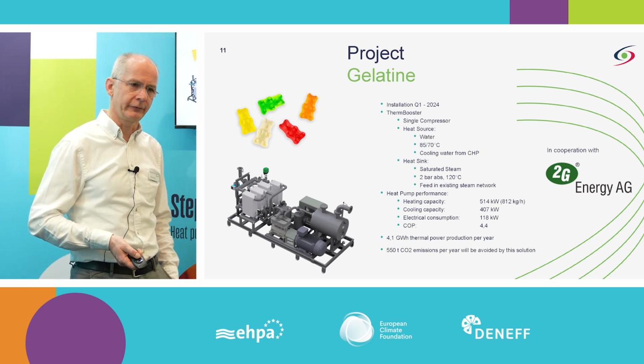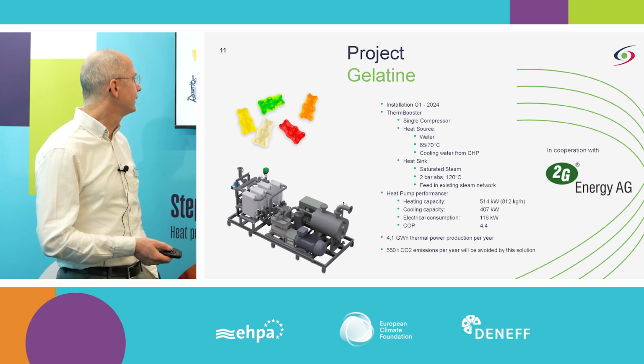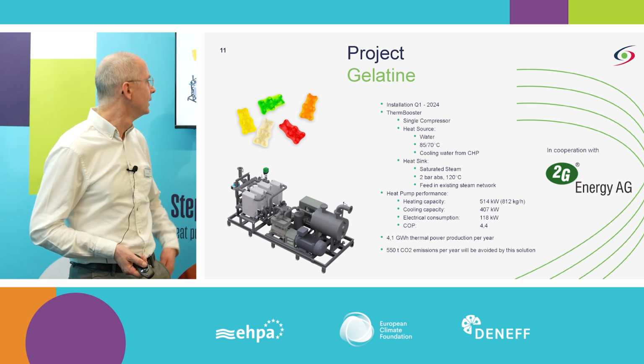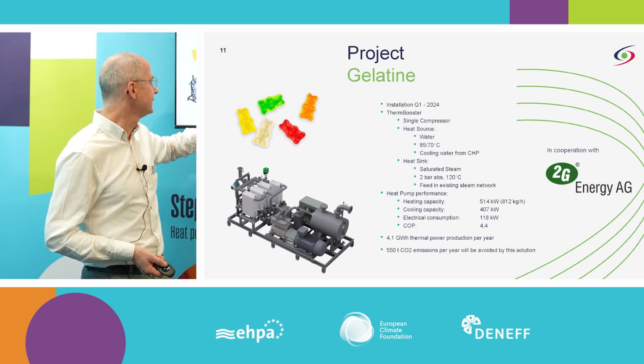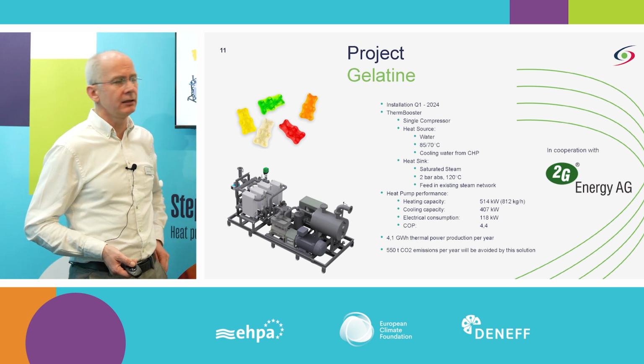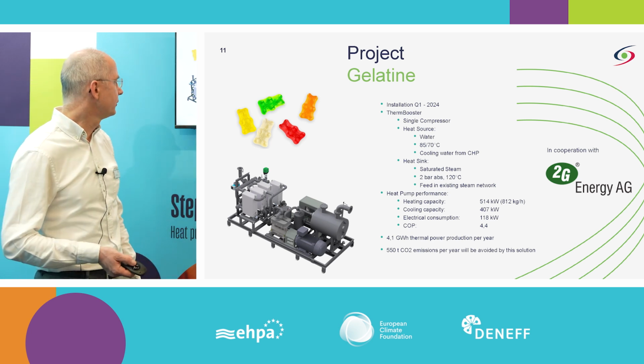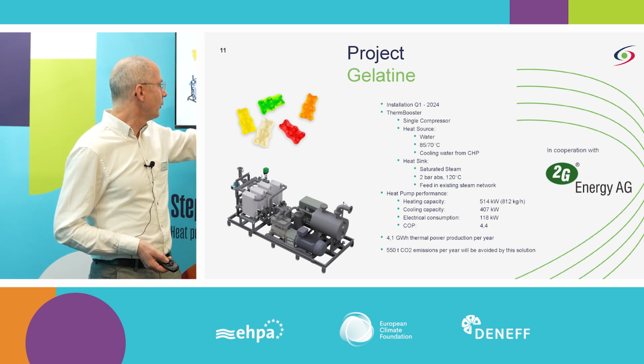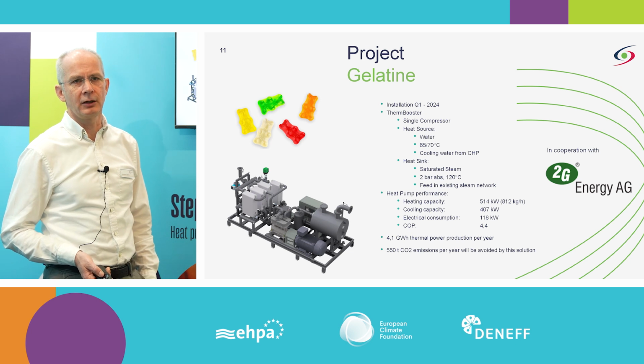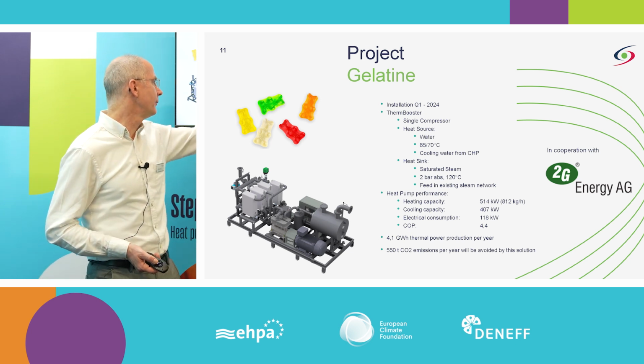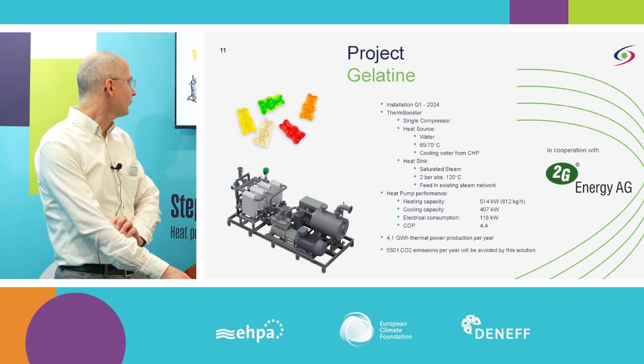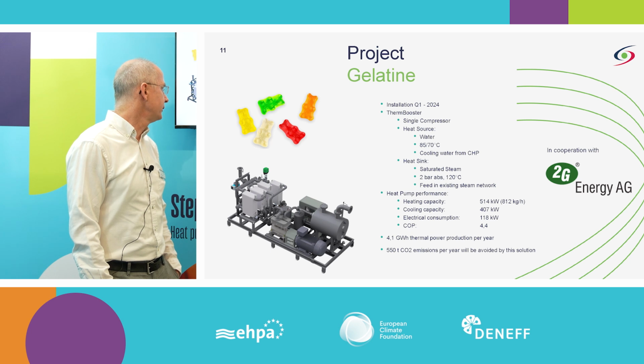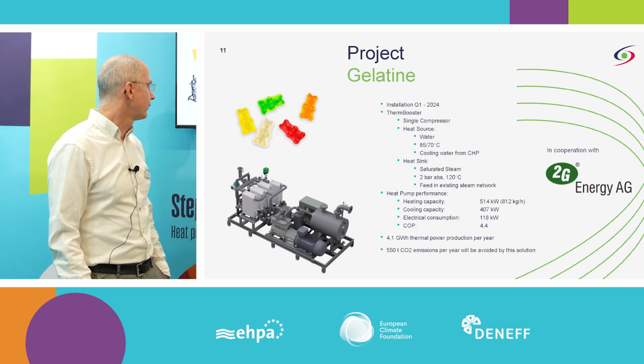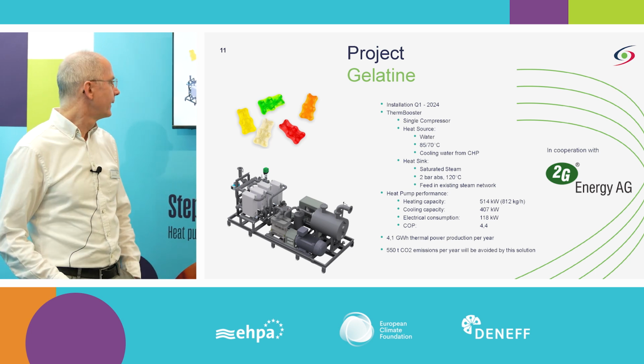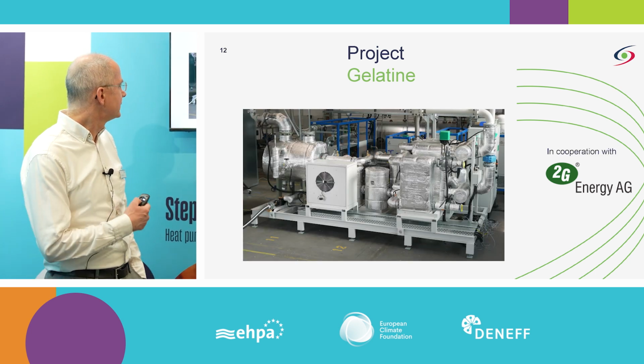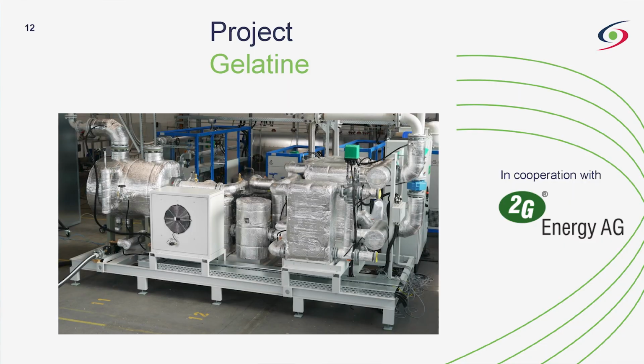So in winter times they do a little bit of floor heating, but in most of the months this is not used. So we take this, cool it down to 70 degrees to cool the engine, and we are producing here 120 degrees steam, which is used to produce the gelatin. And with this one compressor, we have approximately 0.5 megawatt of heating power coming out at a COP of 4.4. And so the CO2 reduction will be in the range of 550 tons. This is a picture of the unit as it was in our lab.